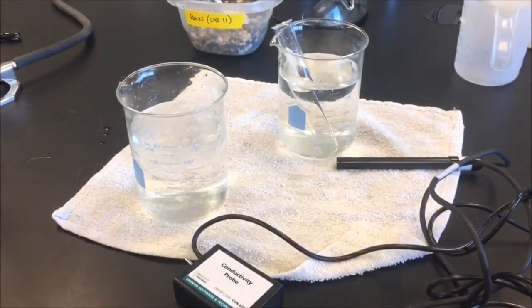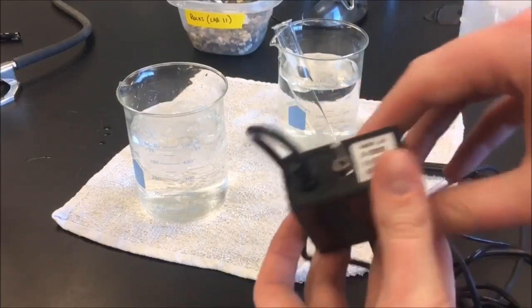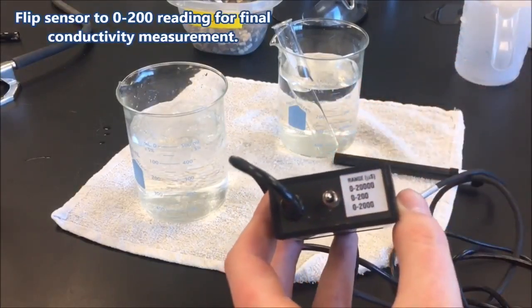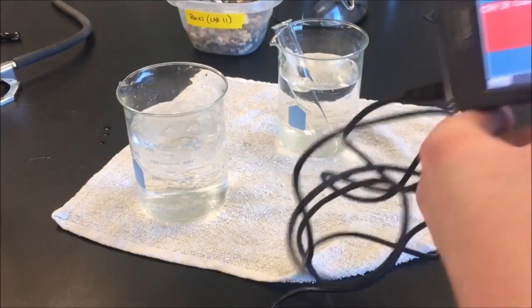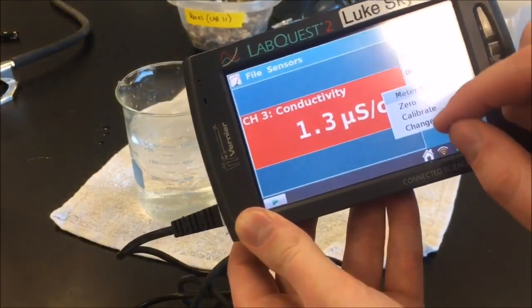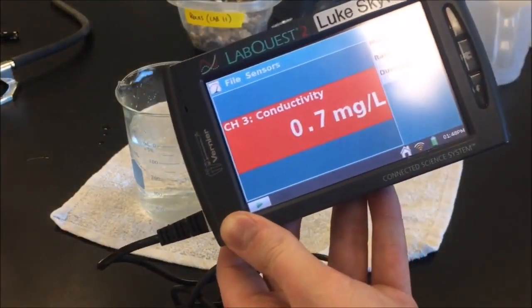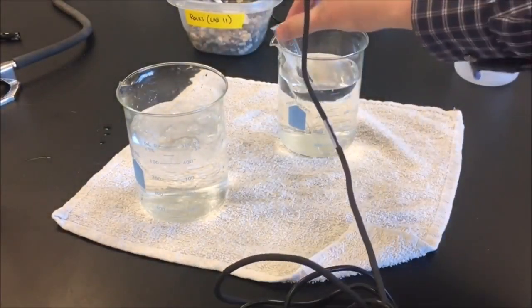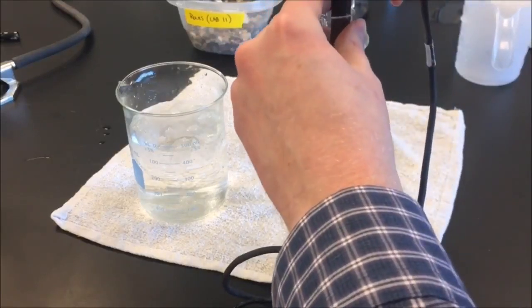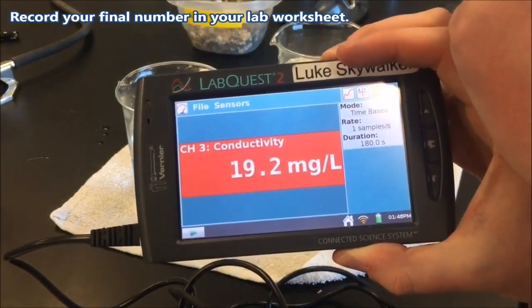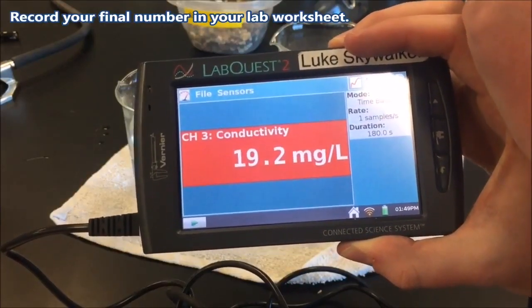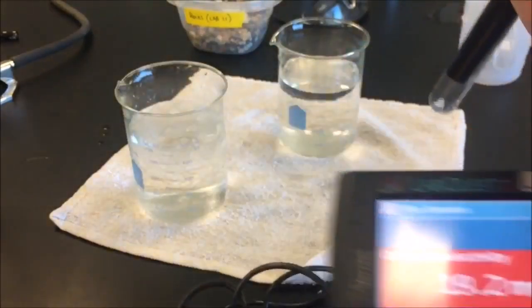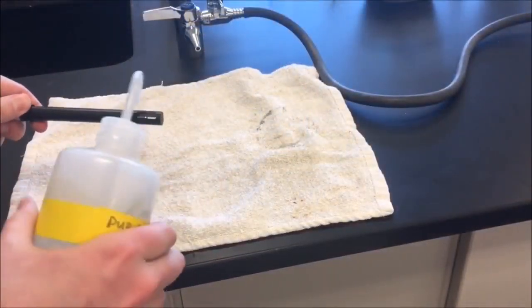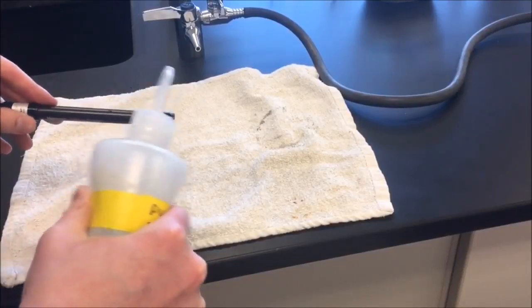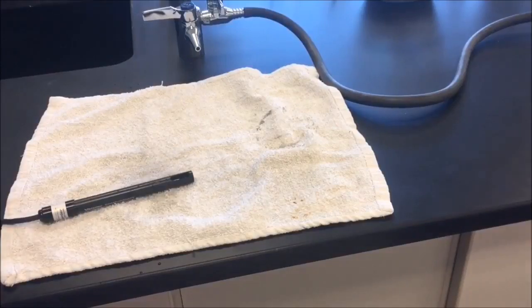So now we'll take our last conductivity measurement. Since we're expecting a much lower number, let's flip our sensor to the lowest setting, which is 0 to 200. Make sure, again, that we're looking at milligrams per liter. And then we'll measure the conductivity of our new solution, which, as you can see, is significantly lower than what we started with, about 19.2 milligrams per liter. One more time, let's spray some distilled water on our conductivity probe and let that dry off a little bit before the lab is done.